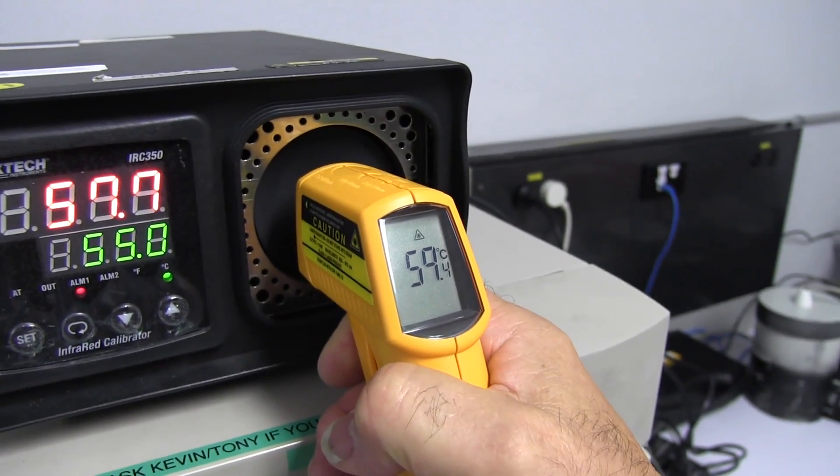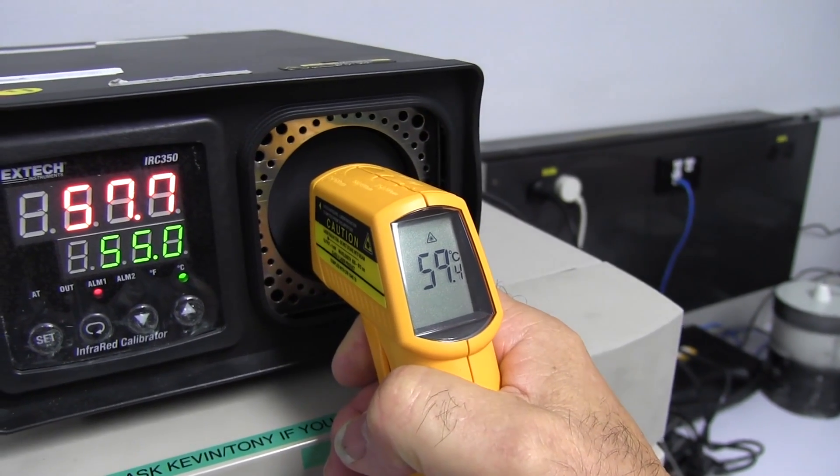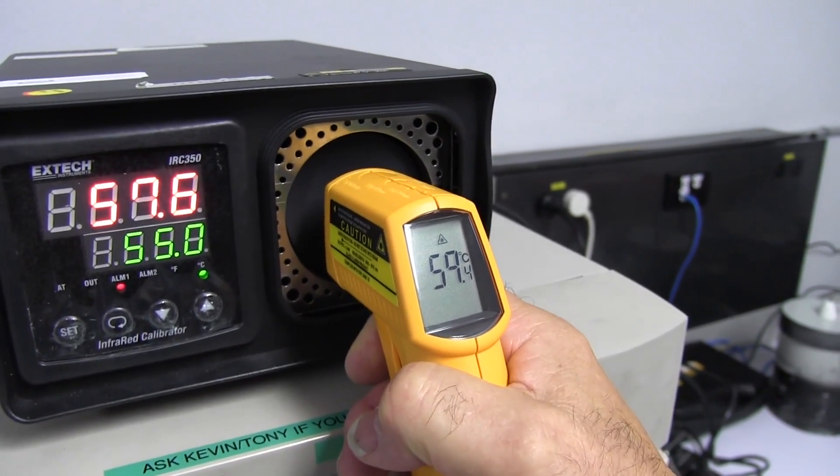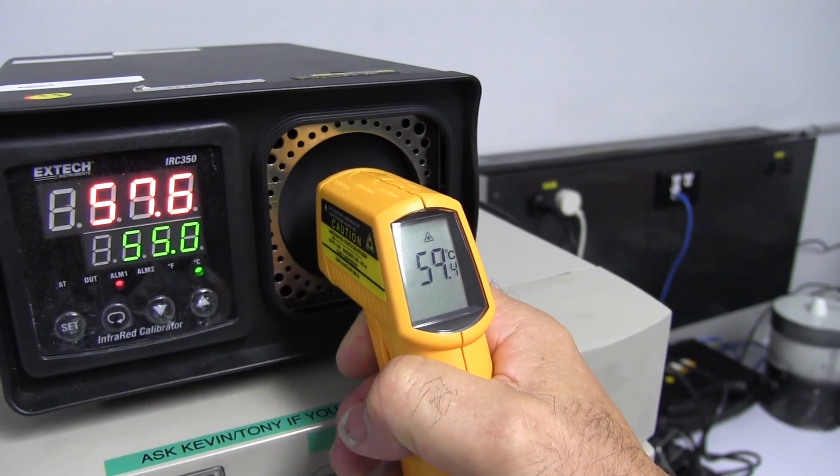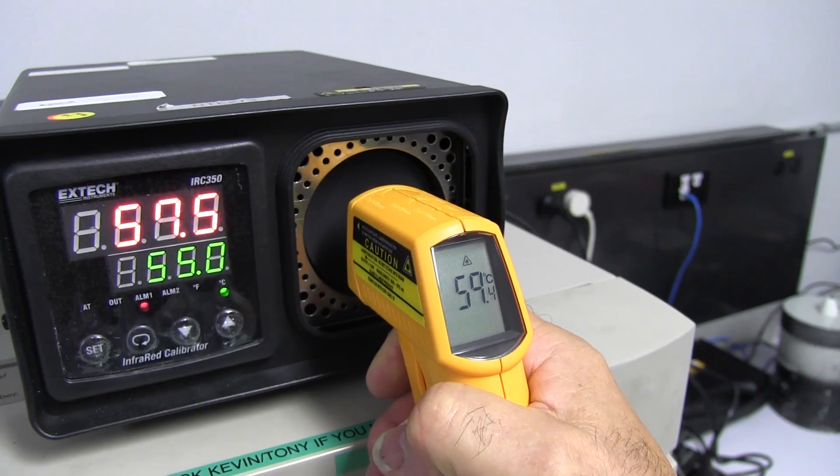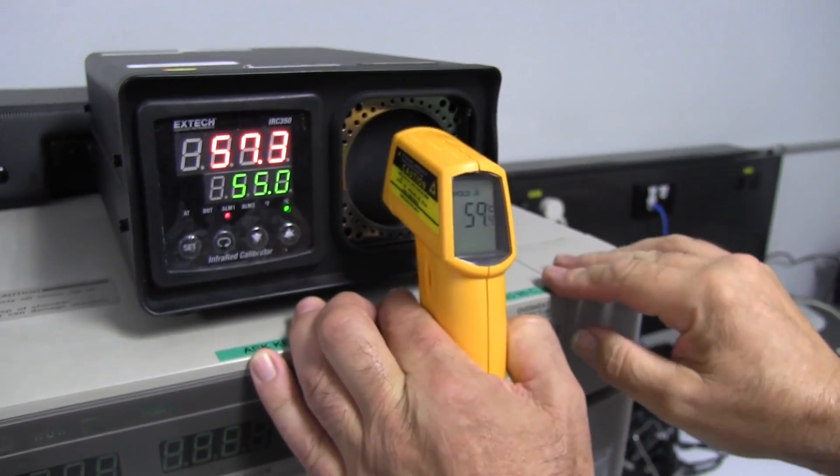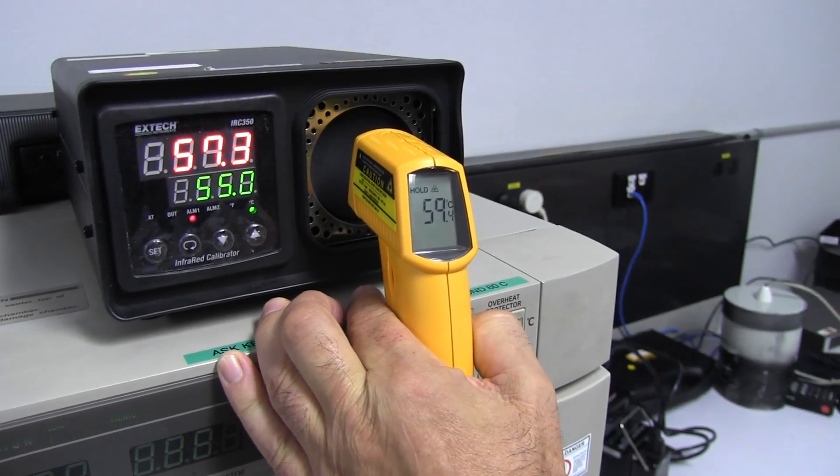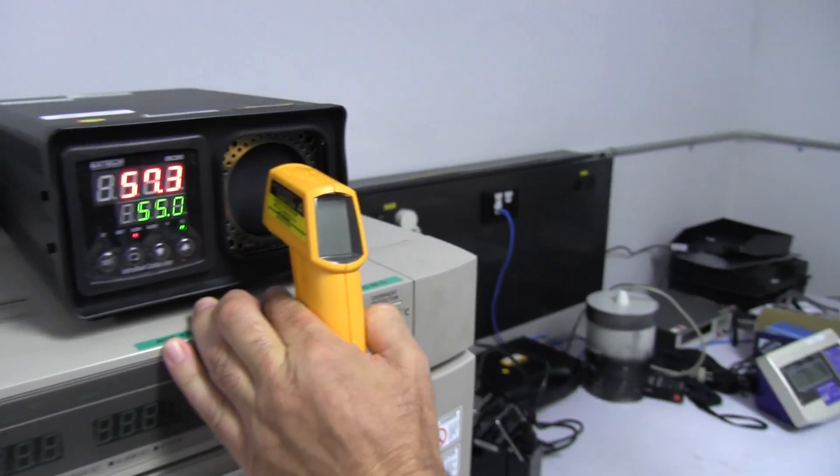These thermometers use about plus or minus two or three. This one's a spec of plus minus two degrees. And this thing hasn't stabilized yet either. We usually leave it for about an hour or so to stabilize. We just switched it on then. So it'll have a multi-term controller in it. So it'll go up, it'll overshoot, come down, get corrected, and then stabilize. So we come back in about an hour, it'll be right.